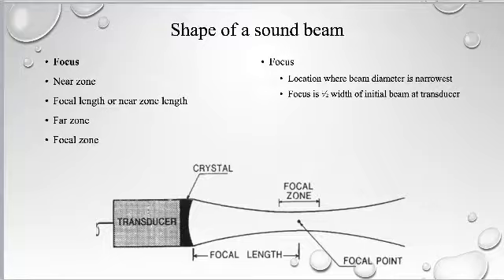Now, what defines the focus? That's where the beam is absolutely the narrowest. And coincidentally, I don't know if it's coincidence or not, the focus is 1/2 the width of the initial beam at the transducer. Okay? So how wide is the focus? Well, remember that drawing I had of the diameter of the crystal? It's going to be half of that. D over 2, right? Diameter divided by 2 is the focus.